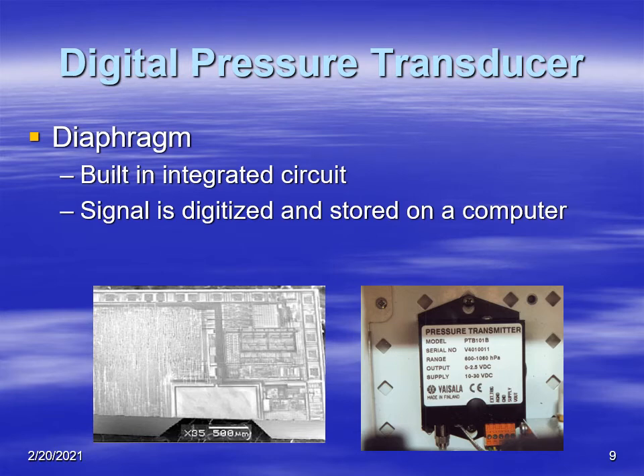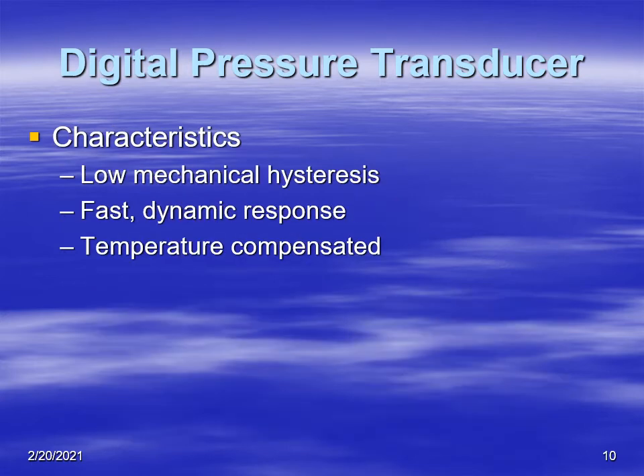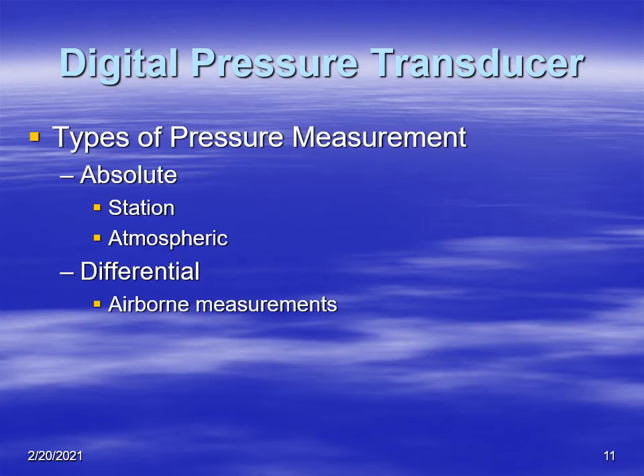These sensors also are typically built right into integrated circuits, so the signal that comes out from them is digitized and stored on a computer. The characteristics of these digital pressure transducers are that they have very low mechanical hysteresis, they're fast, they have a very dynamic response, and they can be temperature compensated also. The types of pressure measured are absolute, meaning either station or atmospheric pressure, or differential pressure, such as a pitot tube measuring airspeed.